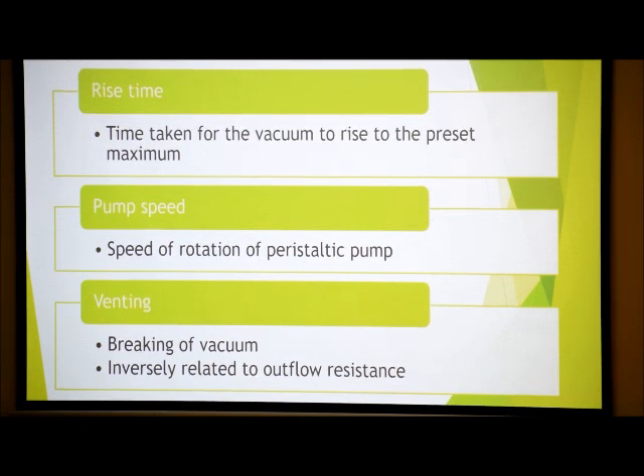So vent is a protection phenomenon. It's in the phaco tip. Vent valves are there that reduce the chances of surge by acting when optimum pressure is attained. They will open up. Either they will allow external fluid to enter into the phaco probe or allow air. So there are two types of vent valves. One is air venting, the other one is fluid venting.